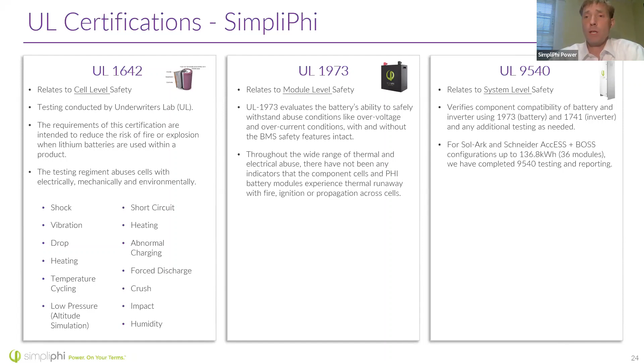9540 includes whole system level safety. So it would include, if you have 4 batteries as part of an energy storage system inside a cabinet with an inverter, the inverter requires a special safety test as well, the UL 1741. It ensures the entire system has adequate safety standards built in. Again, they do fire testing with these to ensure they're safe, and these have to be completed for installations in the US.